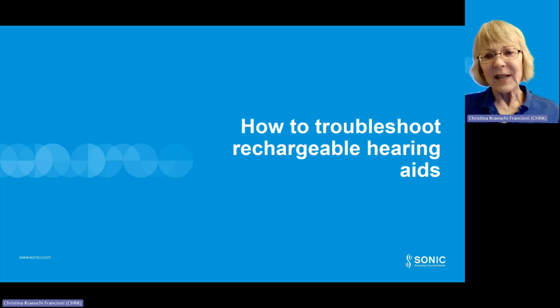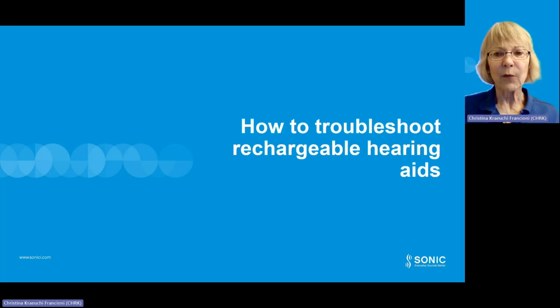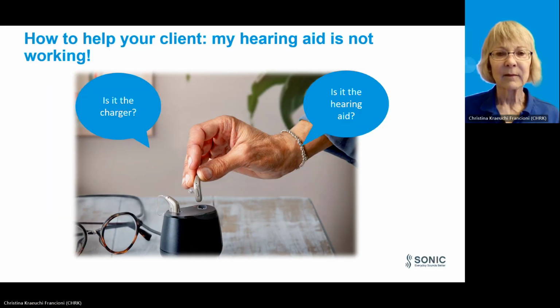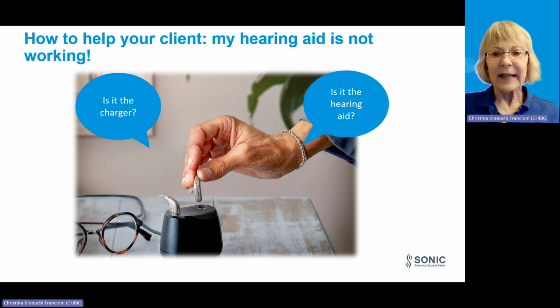Now, if your client reports that their rechargeable hearing aid is not working, we need to investigate if there is something wrong with the hearing aid, the battery, or the charger itself. If you are able to resolve the issue in the clinic, you may be able to avoid sending the hearing aid for service, and your client does not need to be without the hearing aid for an extended period of time. So you can help your client who reports that their rechargeable hearing aid is not working.